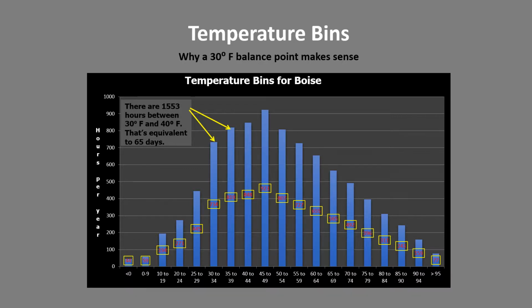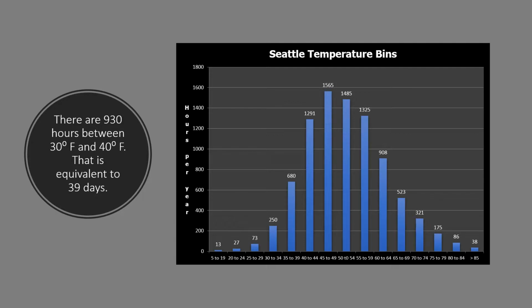What's really interesting is that there are 1,553 hours between 30 and 40 degrees in Boise every winter. That's equivalent to 65 days. So you'd be telling your customers, if you had a balance point of 40 rather than 30, that you're going to have to use your auxiliary heat 65 full days more than if you had a 30-degree balance point. Let's see what it says for Seattle. Seattle, as we all know, is a much warmer climate than Boise, but there are still 930 hours, and that's the equivalent of 39 days. So that's one of the reasons the program really pushes for that lower 30-degree balance point, because so many places in the Northwest spend a lot of hours between 30 and 40 degrees every winter.